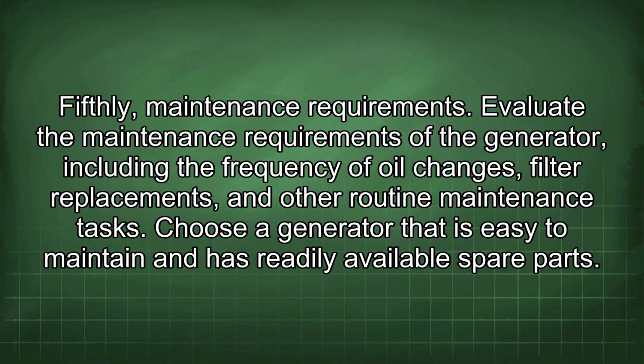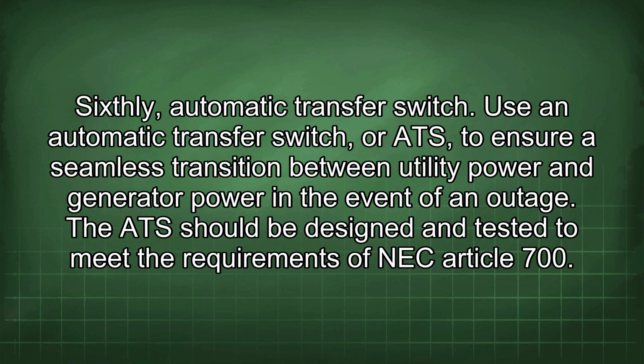Fifthly, maintenance requirements. Evaluate the maintenance requirements of the generator, including the frequency of oil changes, filter replacements, and other routine maintenance tasks. Choose a generator that is easy to maintain and has readily available spare parts. Sixthly, automatic transfer switch. Use an automatic transfer switch, or ATS, to ensure a seamless transition between utility power and generator power in the event of an outage. The ATS should be designed and tested to meet the requirements of NEC Article 700.